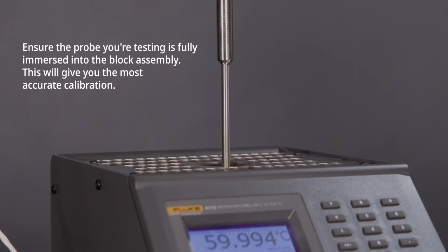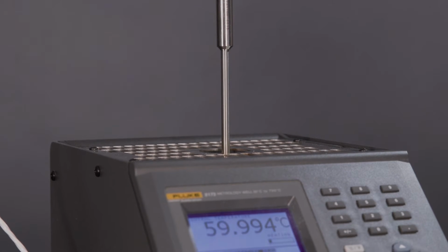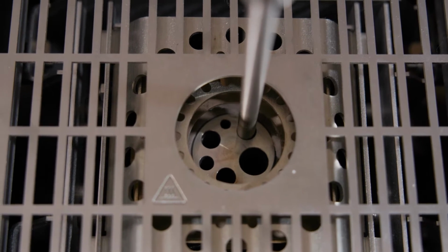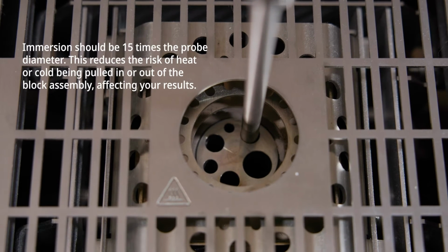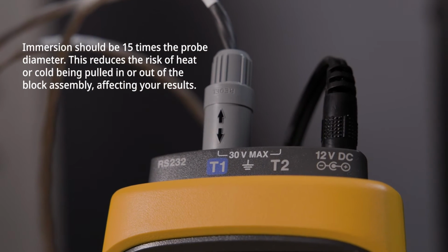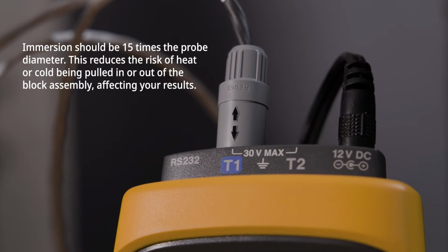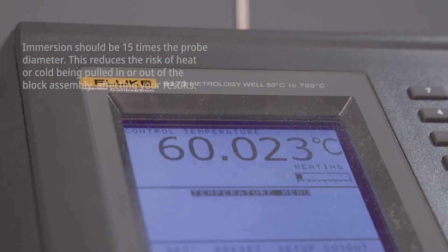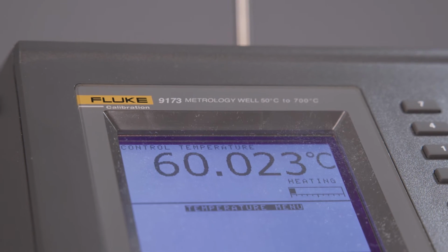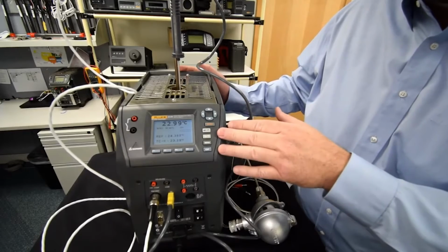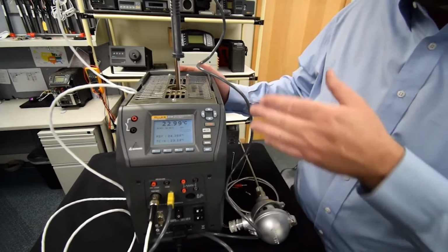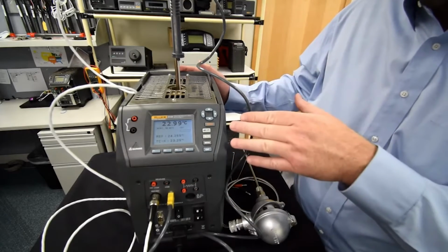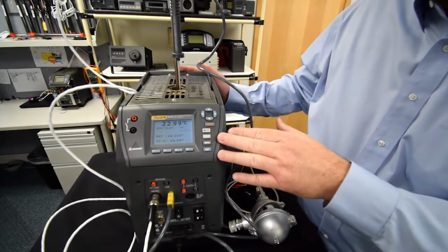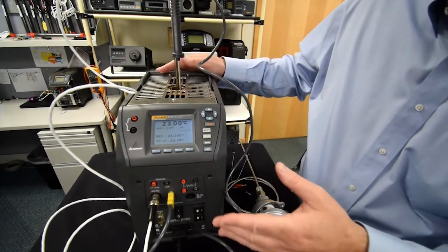This will give you the most accurate calibration. An important rule of thumb is immersion should be 15 times the probe diameter. This reduces the risk of heat or cold being pulled in or out of the block assembly, affecting your results. If your probe is not long enough to be fully immersed, you can use an external reference probe. This will provide a more accurate reading and account for any immersion effects.